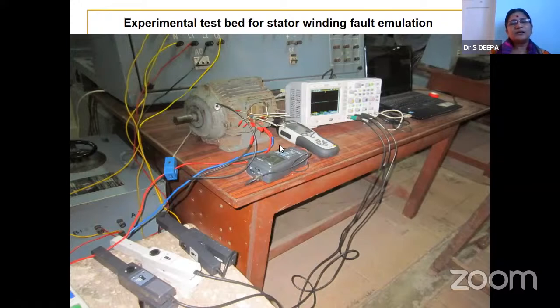Here is the accelerometer to see the vibration of the machine, and here we have the audio measuring device, that is, the sound of the machine. There we use the audio measurement system, and this is also a current sensor of low rating, that is, 1 ampere per 1 volt. Here we have the digital storage oscilloscope. Whatever probe is connected to the oscilloscope, this is the data acquisition system. From the oscilloscope, we connect to the laptop. We have software to transfer the data from the oscilloscope to the laptop, and then we use the data for MATLAB simulation, or we can go for online.